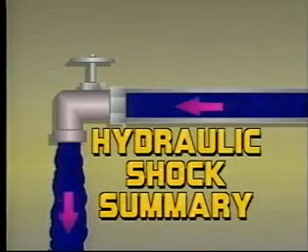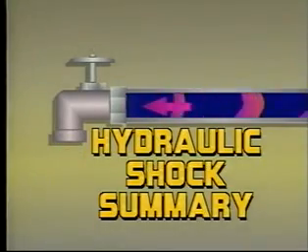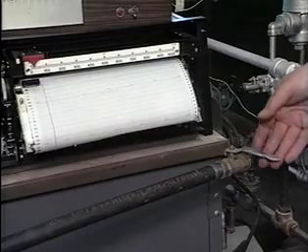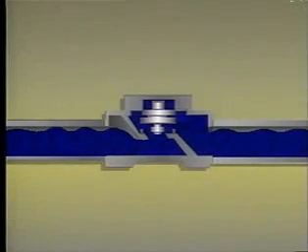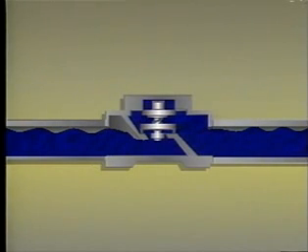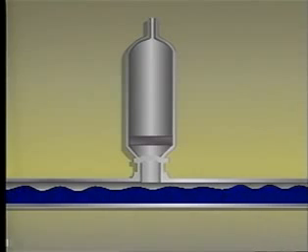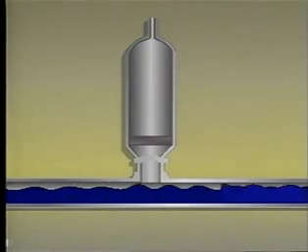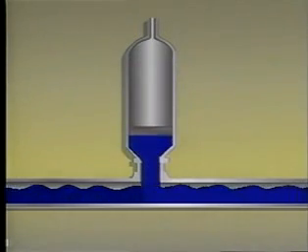To prevent water hammer due to hydraulic shock, avoid suddenly stopping water columns. Ensure slow closure of valves and install spring-loaded, center-guided, non-slam, or silent check valves that close before flow reversal when appropriate. Use water hammer arrestors if necessary, but be sure they are sized and placed correctly and are well maintained.